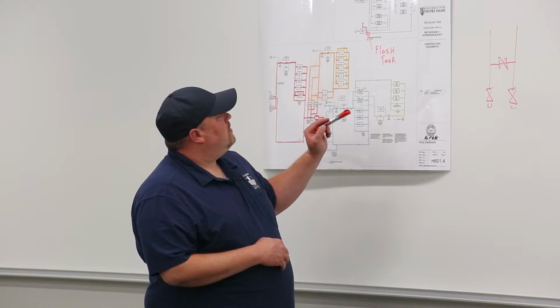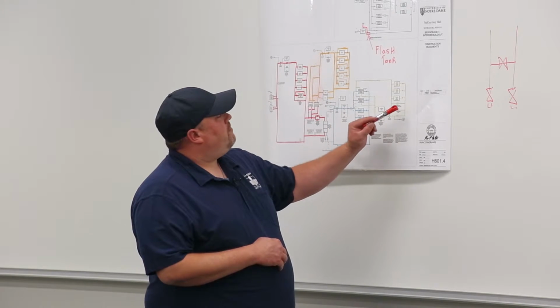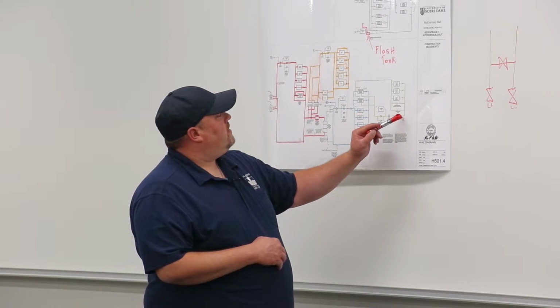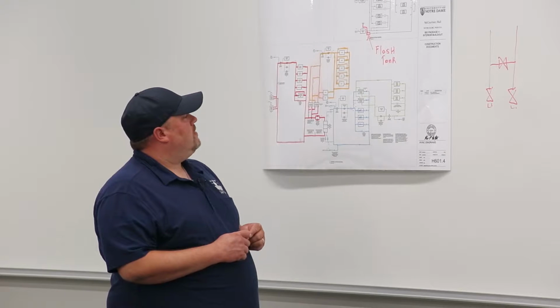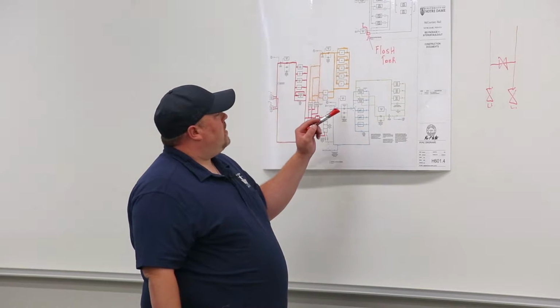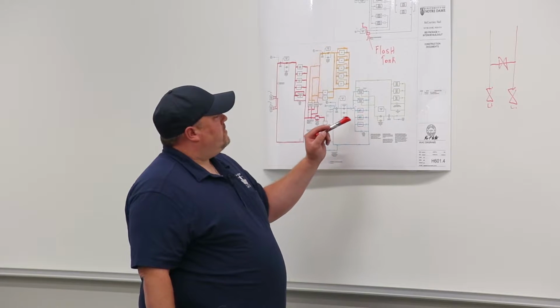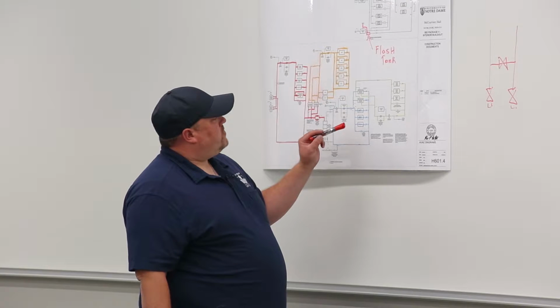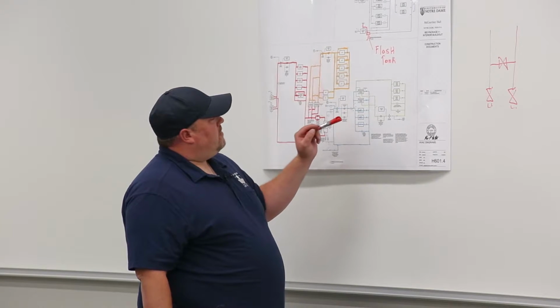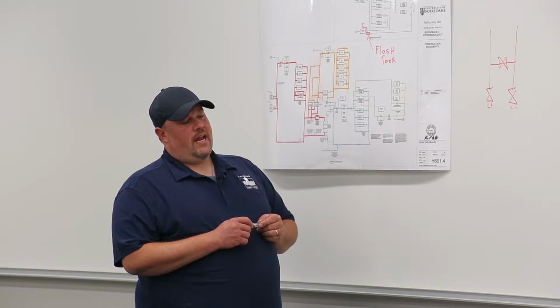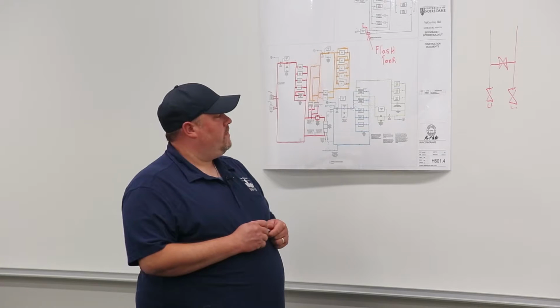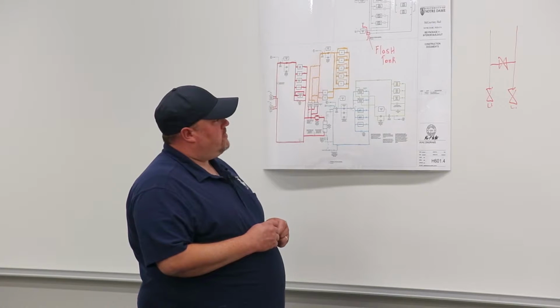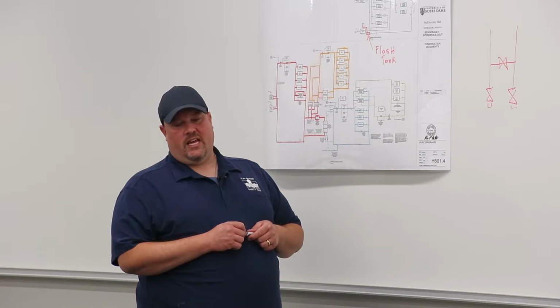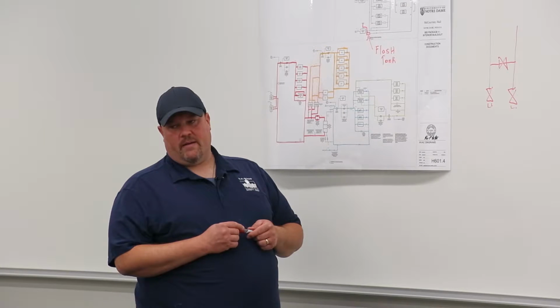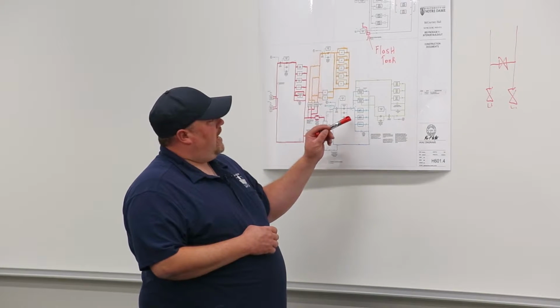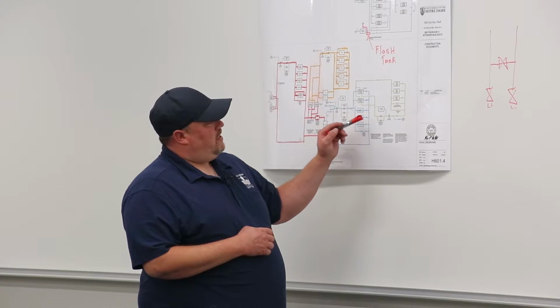As that goes through, it's just got a normal pressure differential for backup and a bypass, and that's basically the loop for our processed chilled water. Going back to the regular chilled water, it goes through our lab air handling units and office air handling units and fan coil units. Most of the fan coil units, you've got your air handlers upstairs. The air handlers located in Area A, the east wing of the building, and Area C, being the north, are the ones that control the labs. The unit located in Area B, in the center of the building, is actually for the offices.